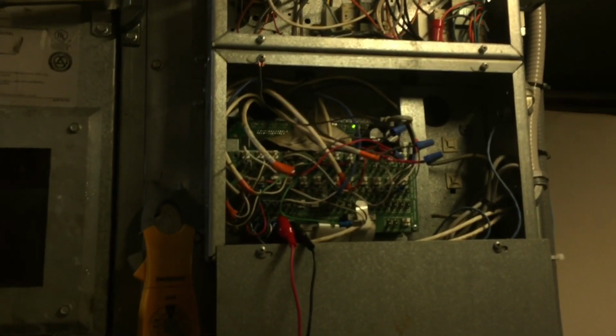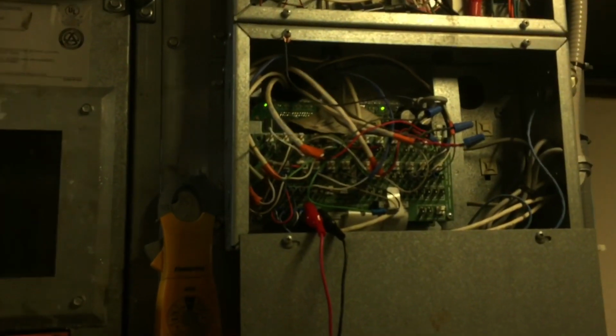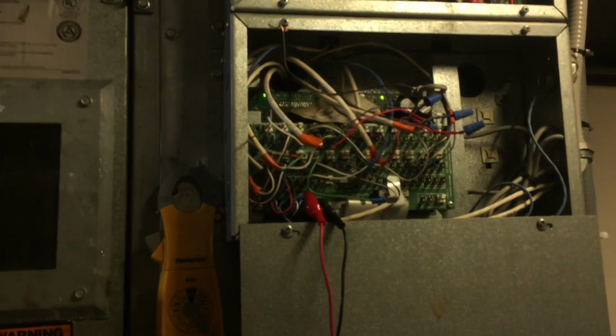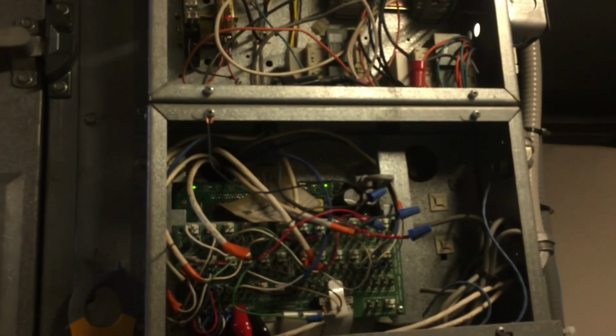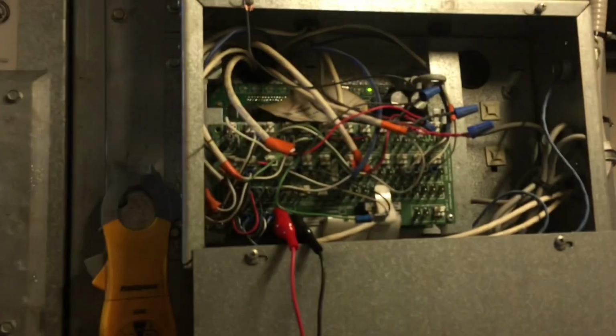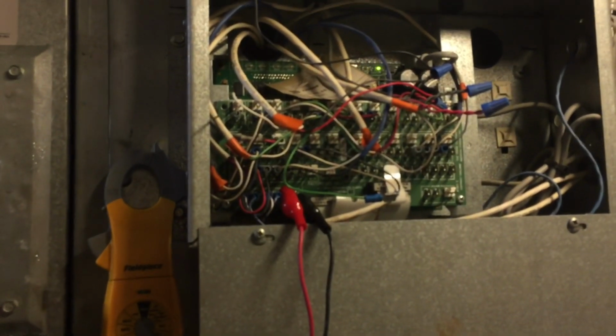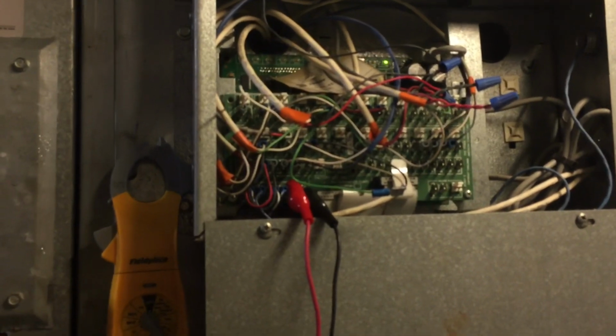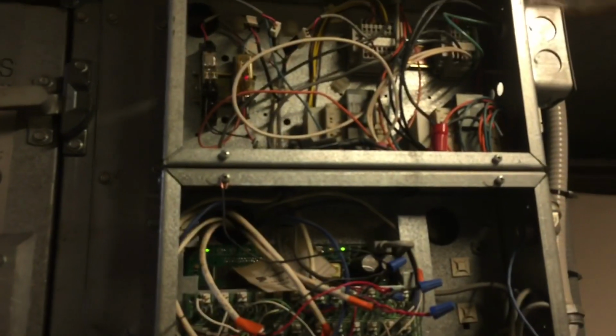So be aware that when you have controllers that are powering multiple actuators and you have multiple transformers, you have to make sure that the signal that is driving your device has a ground, or is a common ground to the other transformer that is in the device.